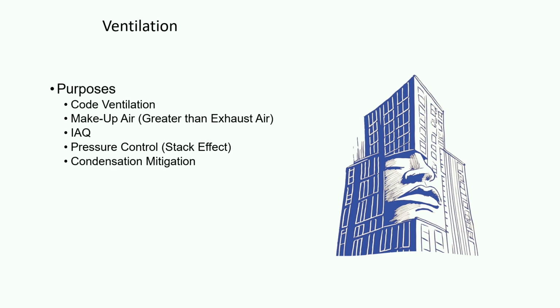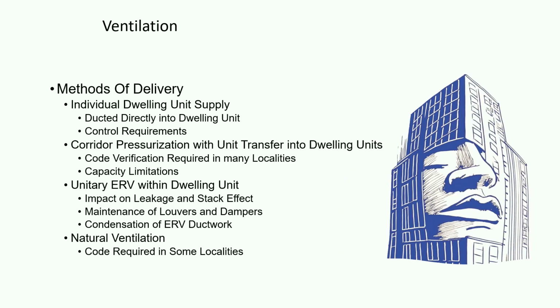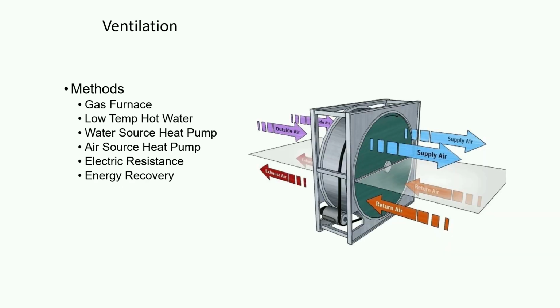But then again, how does that change your thermal profile of the total, looking at geothermal specifically? Because we need to understand that if you're going to size a ground loop that's going underneath the building and going to be there for the next 80 years, right? So again, a lot of different ways to get the ventilation to the spaces. I mentioned ERVs is important. Obviously, you can still do some natural ventilation, but harder to meet some of the codes with natural ventilation. All right.